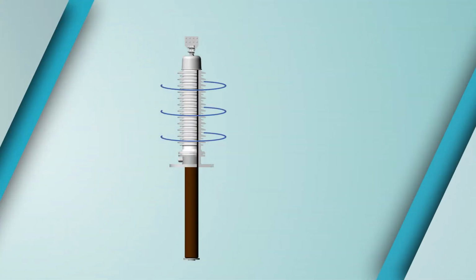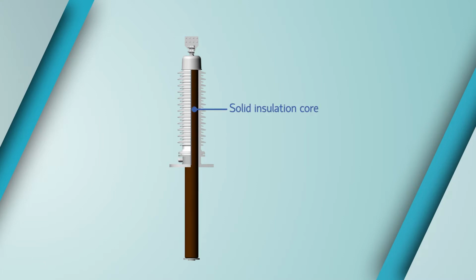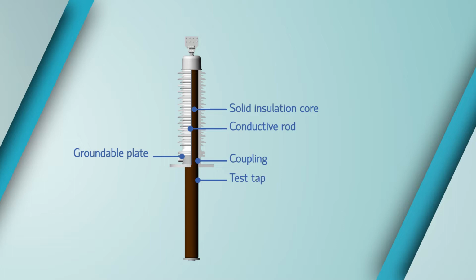The bushing comprises the following structural components: a solid insulation core, where the insulating paper is wound around the central pipe and impregnated with resin. RIP insulation as such. Wound paper is divided into layers by means of conductive plates in order to level up the electric field. A conductive rod inside the central pipe. A coupling mounted on the insulation core. A test tap linked electrically with groundable plates of insulation core. A mounting flange intended to secure the bushing on equipment. The flange is fitted out with eye bolts.